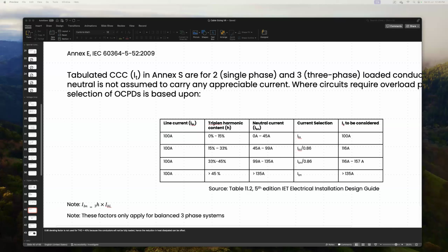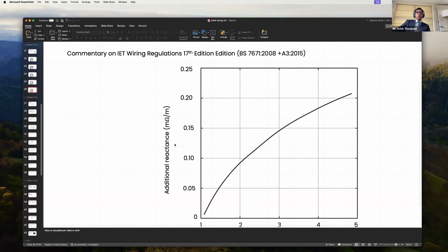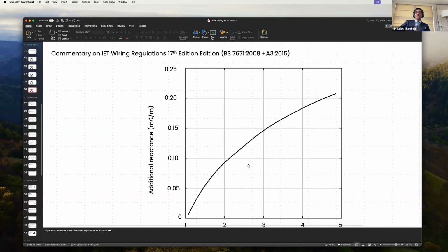Krish, do you have any answer on this? I would say that instead of designing for bunched and looped up cables, lay the cable properly first, and then you design, and it should be designed for proper laying. Of course, if you decide to talk about increased separation distances, that is a separate story, like I showed you earlier. As the distance between the cables increases, reactance increases. But because they are bunched and laid poorly, we cannot just somehow make some compensation for it. You need to install properly.